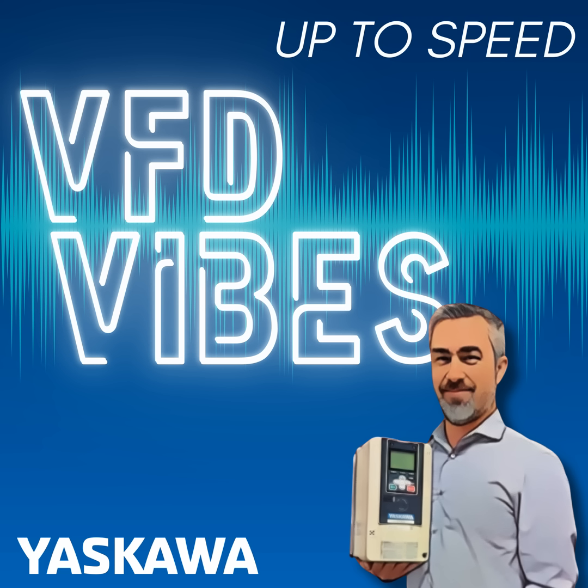When you talk about traveling upstream, though, the harmonics we're talking about today are different than when people talk about EMC, correct? Oh, yeah, Greg, you bring up a different subject entirely, and this pertains to variable frequency drives and just how a drive is designed. The nonlinear current draw and the switching we're referring to when we talk about a switching power supply, we're talking about the front end, the input side of a VFD.